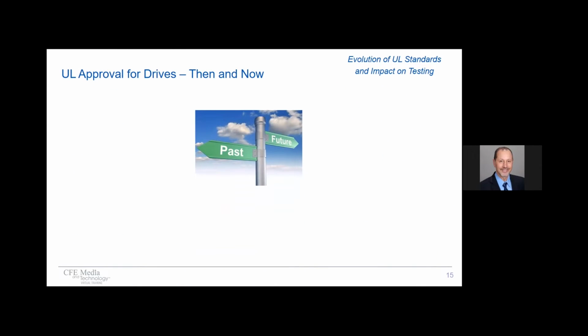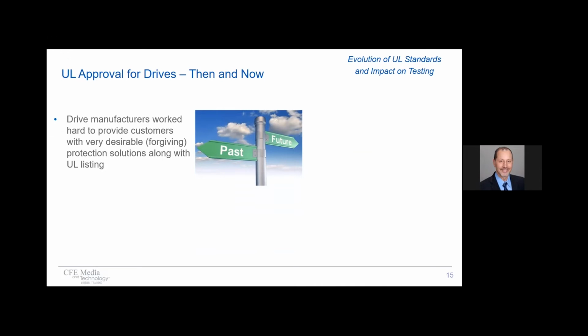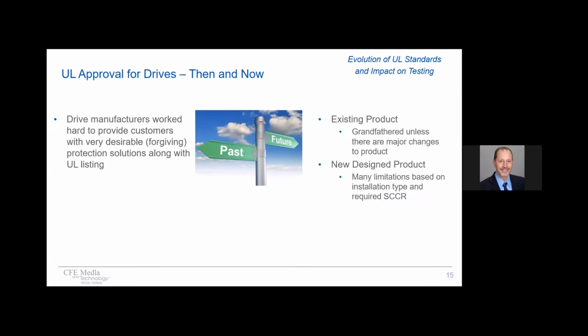So we're going to go into some detail, but related to this, the path to UL approval has definitely changed over the years. In the past, drive manufacturers worked hard to provide customers with very desirable or forgiving protection solutions along with the UL listing. But things are changing as we move into the future. Existing product that's been in the market for quite some time is grandfathered unless there are major changes to the product that UL cares about. But for newly designed product, there are many limitations based on the installation type and the required withstand rating or SCCR rating. Like many other product categories, UL has specific standards for power conversion equipment like drives, and the evolution of requirements has certainly affected these standards.